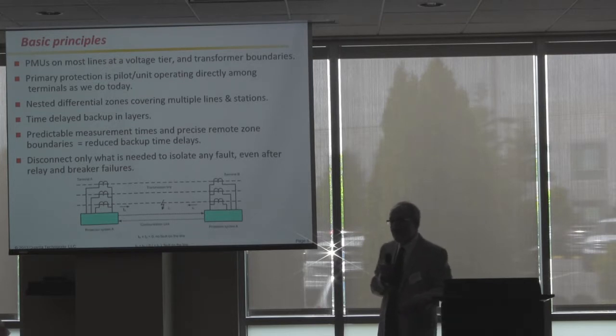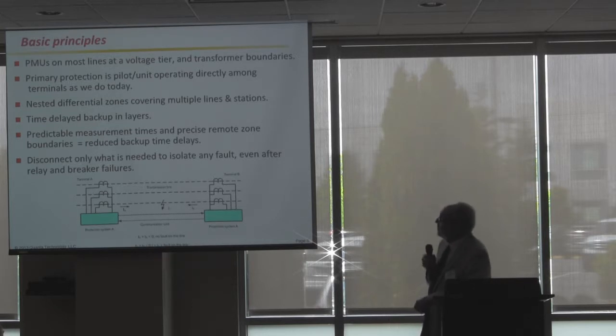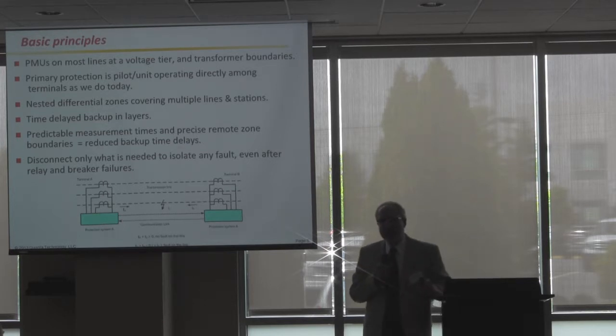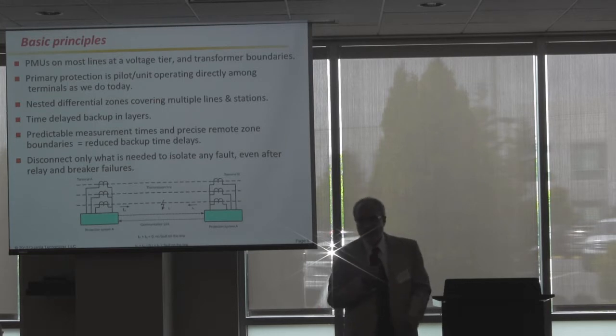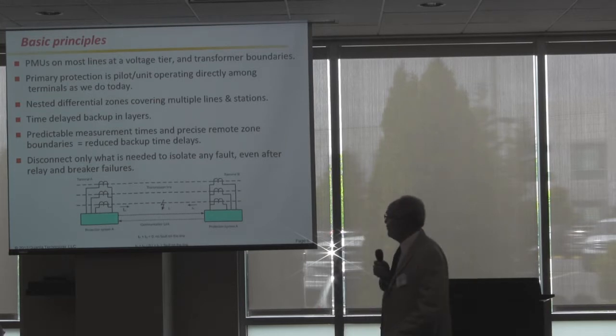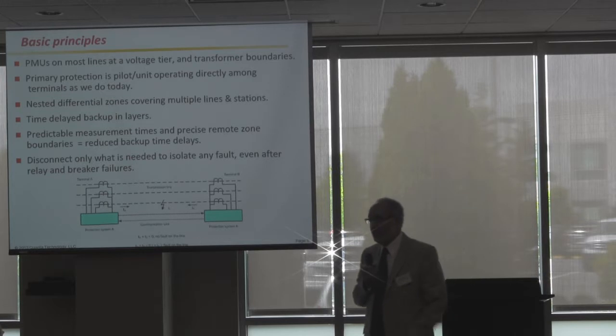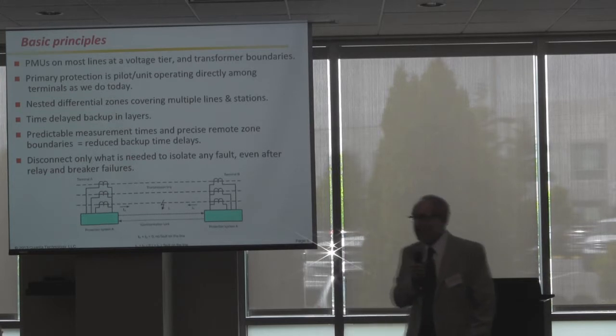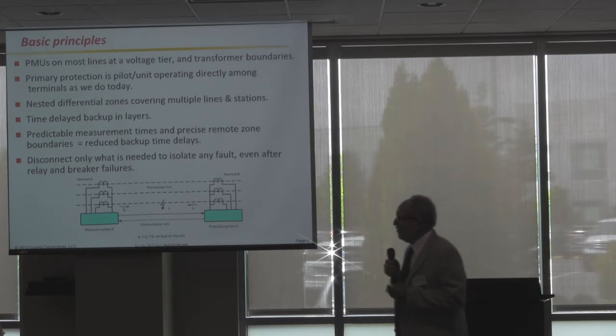Because the measurements are not available at the same place and the same time, we need to know the timing. We either measure the delay, or we have the time tags in the case of synchrophasors, which is beautiful and simplifying. We can take the thing we already do and have been doing for many decades on transmission lines, buses, transformers, and we can do it across the whole power system, nesting our zones of protection using these phasor measurements of current. There'll be other things we can do with voltage that I'll mention briefly. There are beautiful advantages to doing this.